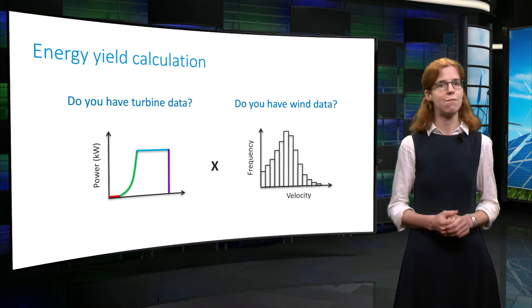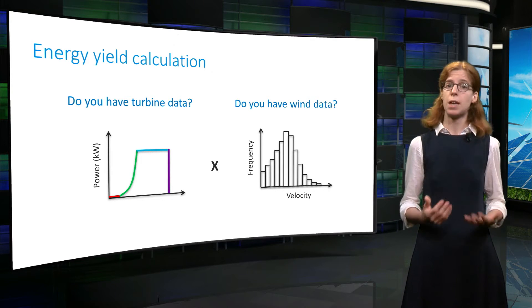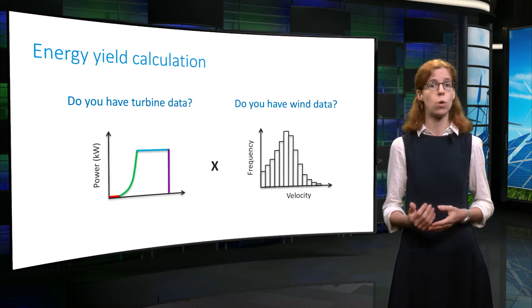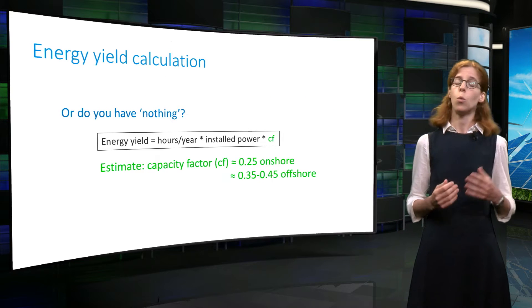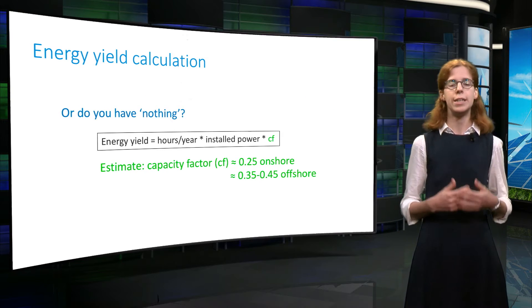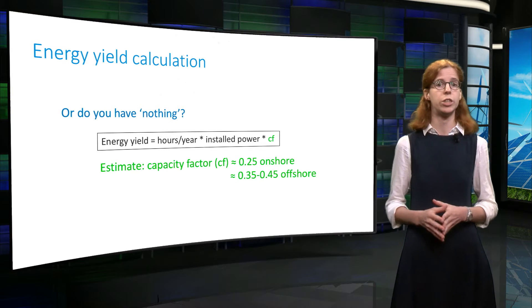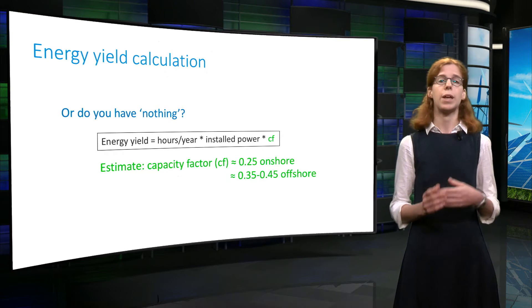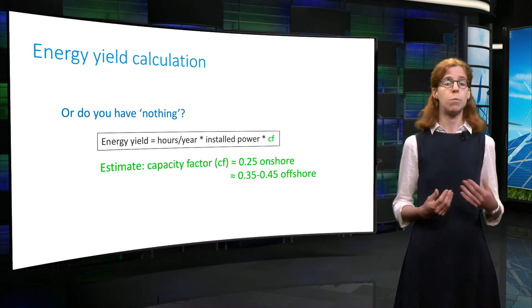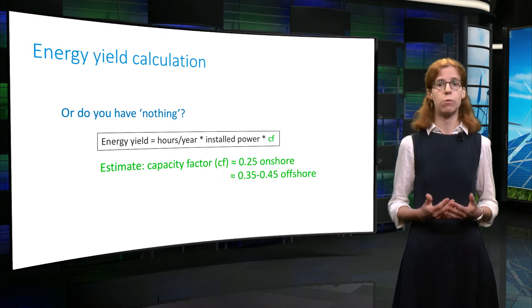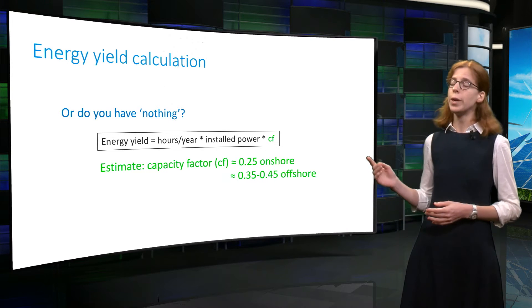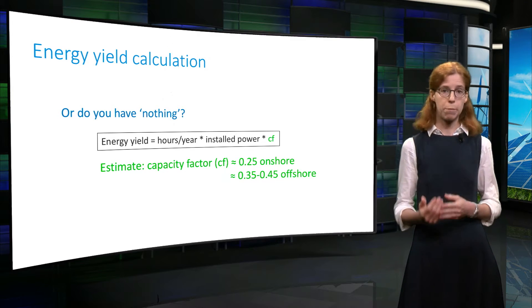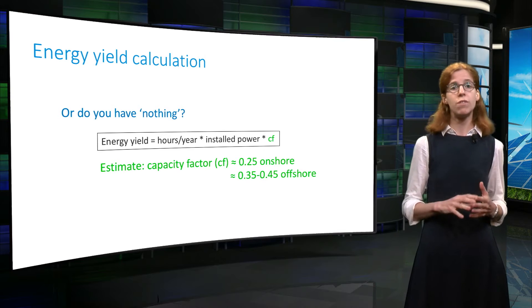But what if we don't have this information? It is indeed sometimes very difficult to get wind speed measurements at the location where we would like to install a wind turbine. Without this information, it is still possible to compute a rough estimate of the energy yield using the capacity factor. Remember that the capacity factor is an indicator of the percentage of time a wind turbine runs at full power. So, knowing the rated power of the turbine, we can multiply this value by the capacity factor to get a rough estimate of the energy yield.